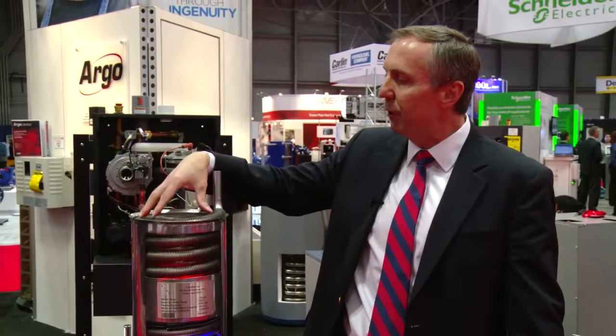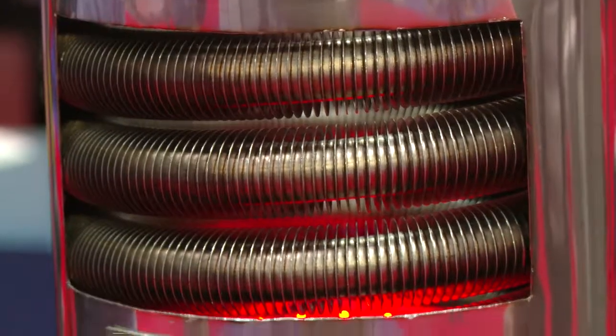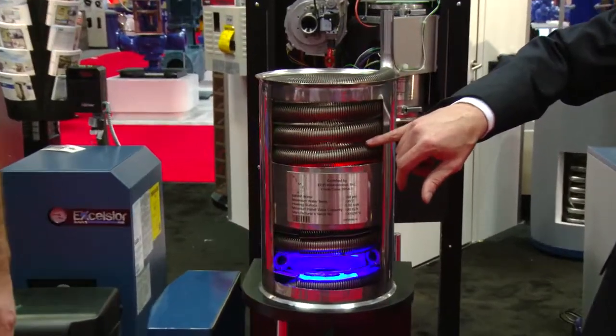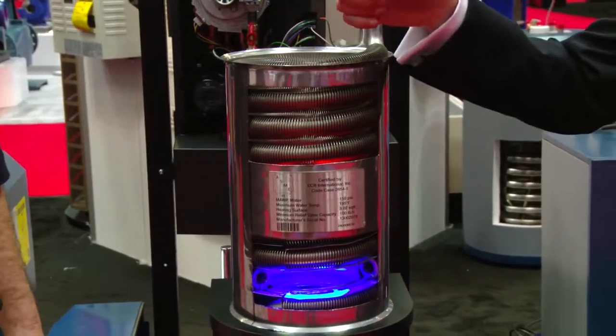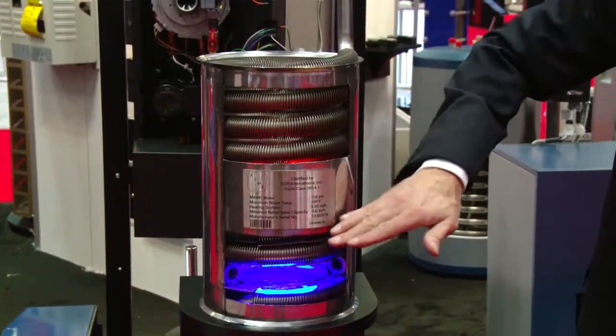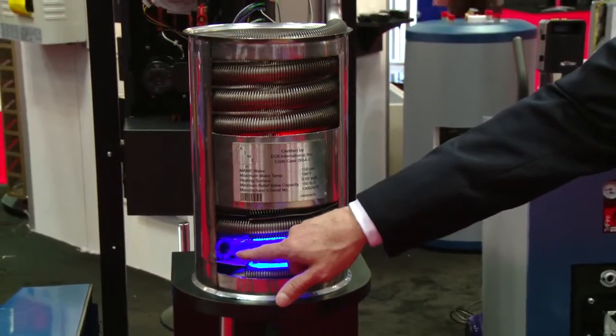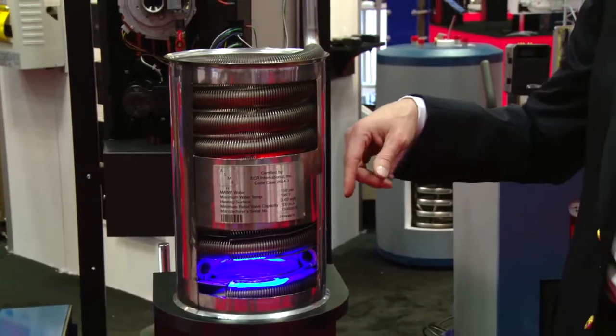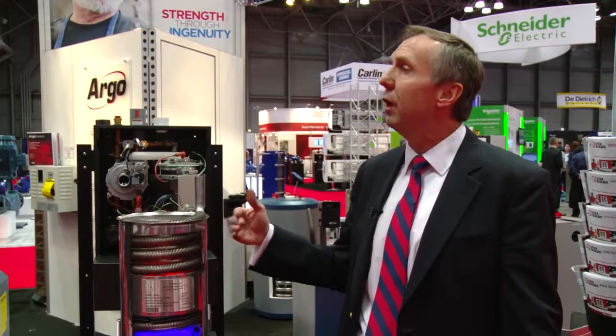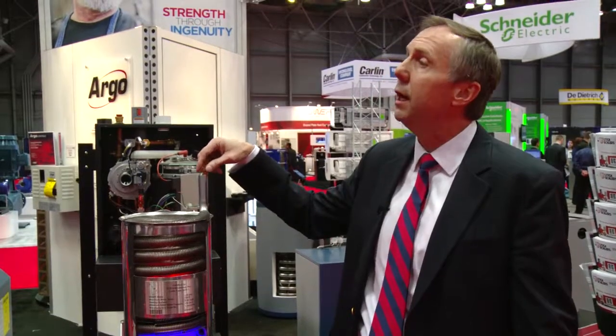Because as you start to condense, you're going to possibly get some precipitants. Those precipitants are allowed to wash out and come down through the condensing zone, and as you can see, the fin spacing is wide open. Why is that important from a service standpoint? You can hit this with air, and you can easily see if there's any plugging going on. This is the area in which the flame is embedded, then as we get into the condensing zone, we also have a very wide open tube diameter. There again, it reduces the pressure drop. So unlike some heat exchangers that are more compact, with tighter flue spacing, this is a lot easier to service, and it tends to act in a self-cleaning manner on both the flue-way side as well as the waterway side.